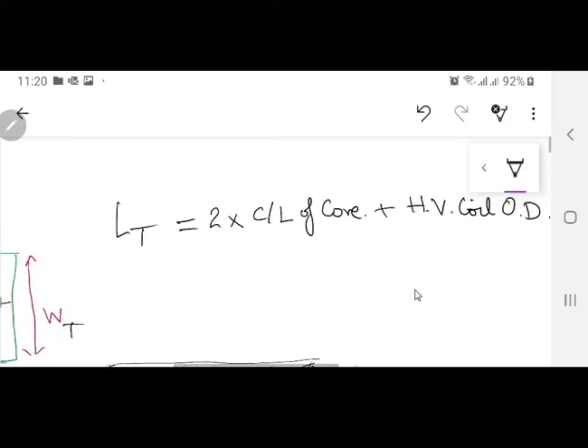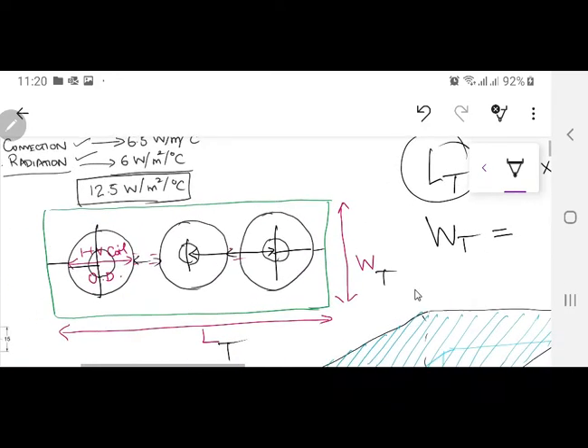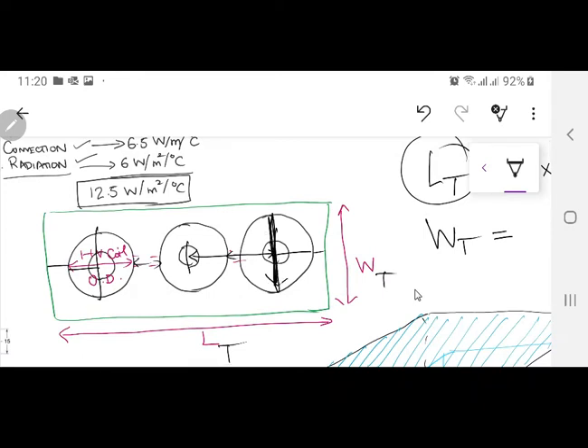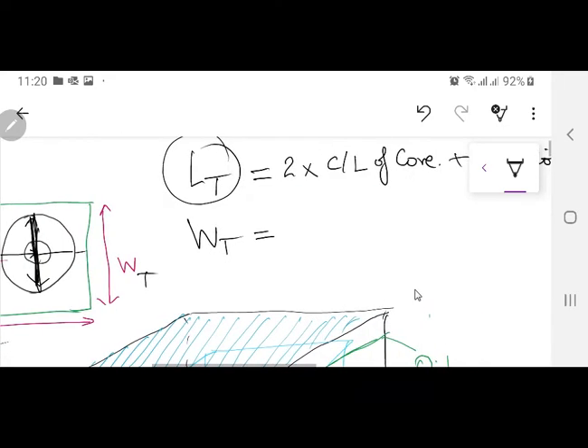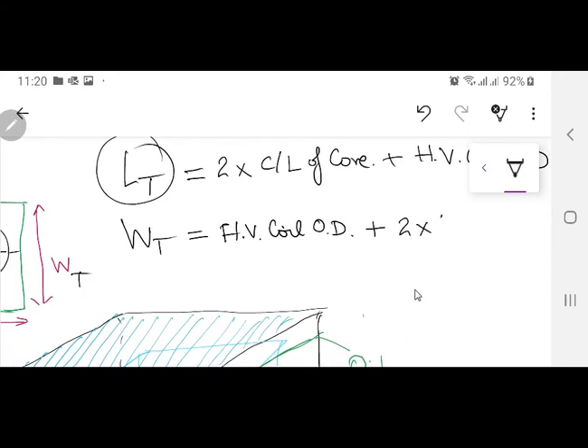So your L of T, the length of your transformer tank, is equal to this value. Now WT, width - width is equal to this distance plus some clearance. This distance is the outside diameter of your high voltage coil. So the width is equal to the high voltage coil outer diameter plus 2 into 40 mm. Again, this is a variable value which will change whenever you are designing a different transformer.